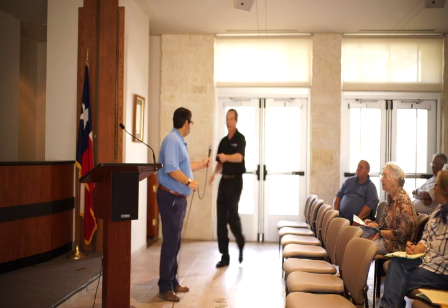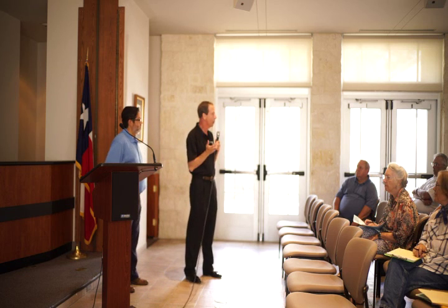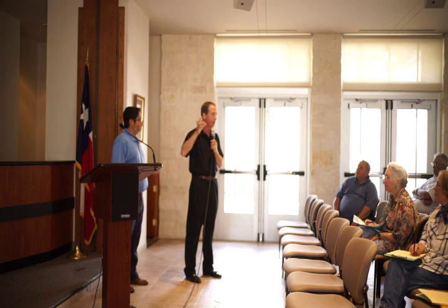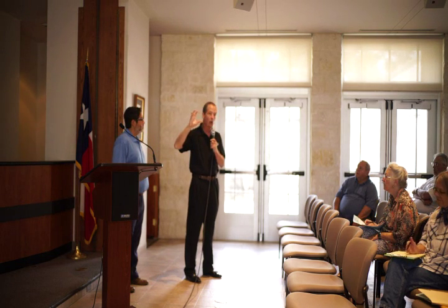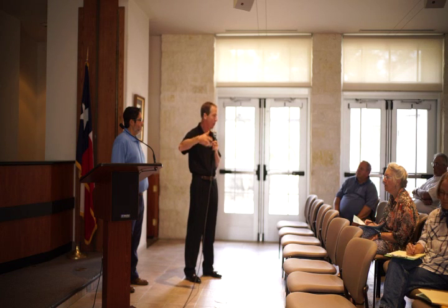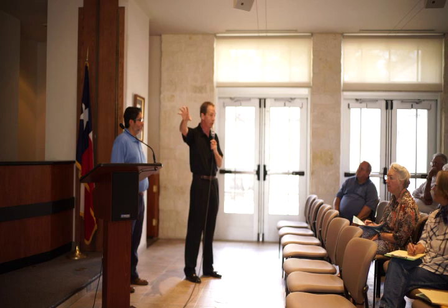I'm Tom Merrick with Silver Spring. A relay is just a repeater, so it gets data from the meters in the area and then it sends it back to the access point. The access point is the actual thing that will send all of the meter reads back to CPS Energy. So a relay makes the signal stronger in an area where it needs to be stronger and repeats the signals, and the access point actually takes it out and hands it to CPS for billing.